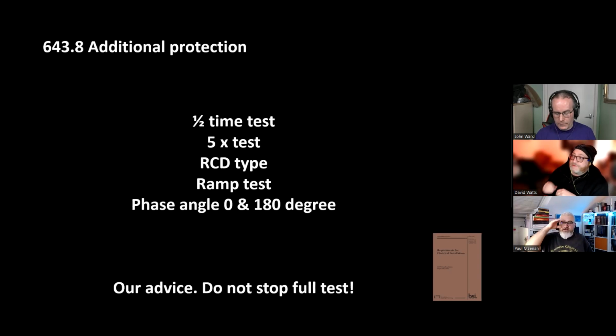So how about this then? In the next edition, why don't they change it so you test at the terminals at the end of line when you're doing initial verification, but on an EICR you have to test end of line to verify the safety performance has not been impeded by the connected loads. But then you've got the connected loads, and then you've got the issue of equipment damage and all this other stuff. And what manufacturers don't want is damage. What equipment damage? It's a low current test. You've seen what they've said.